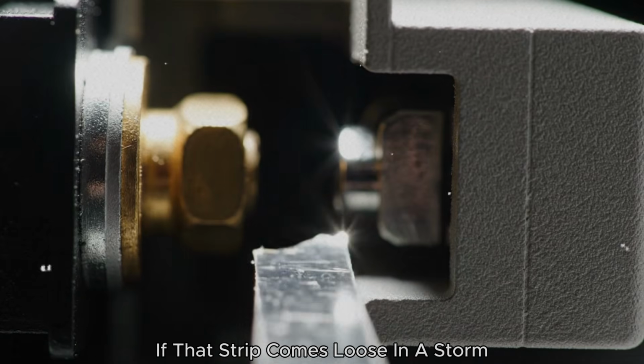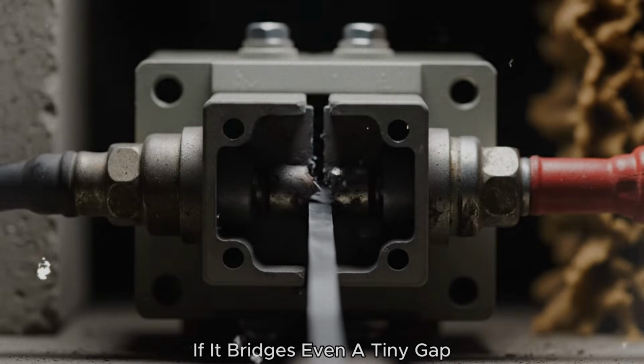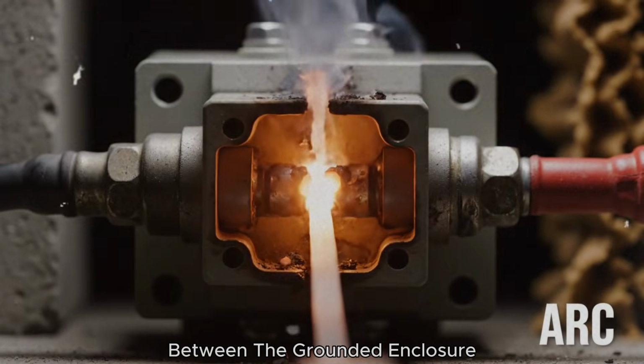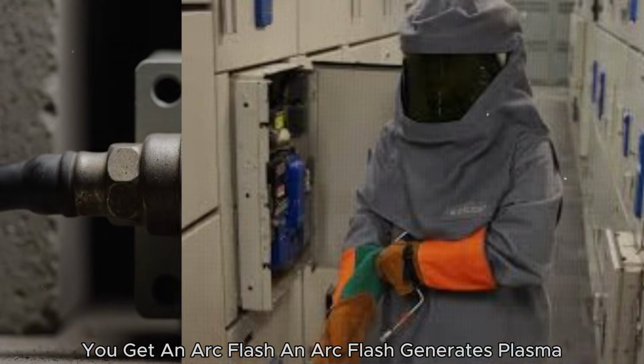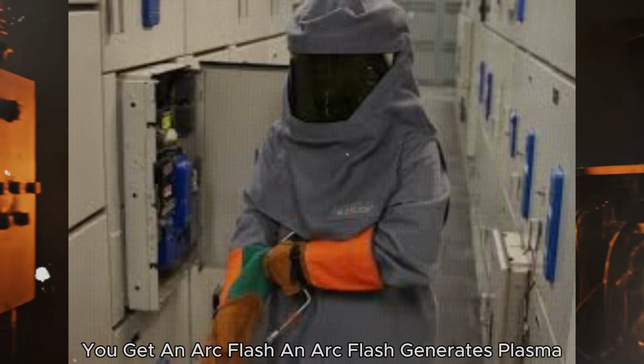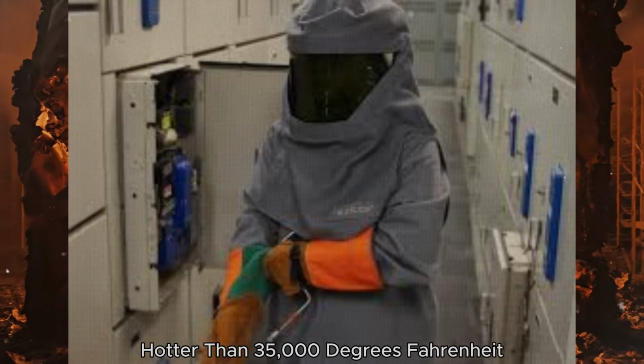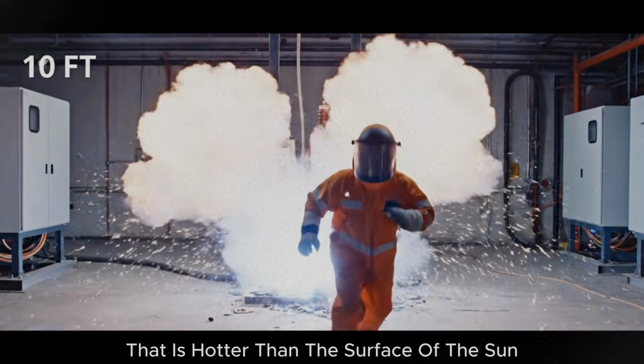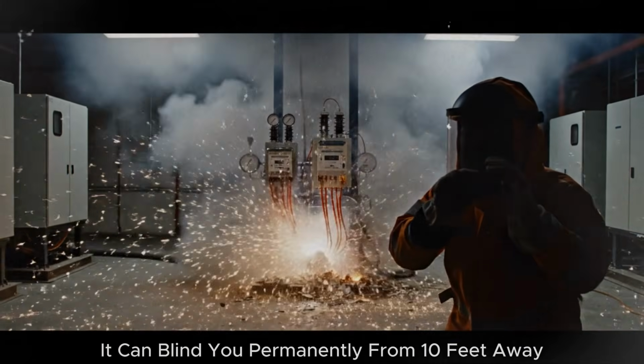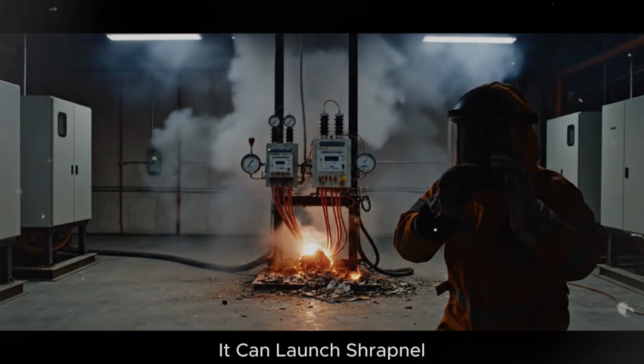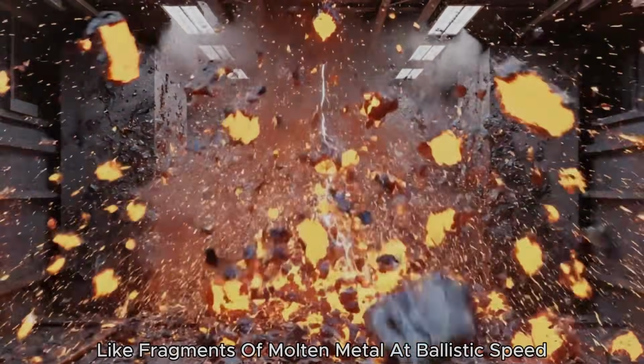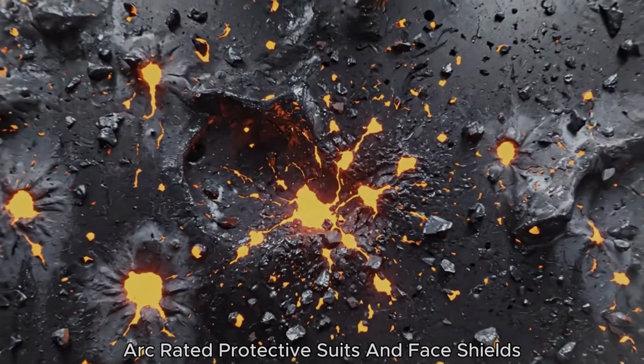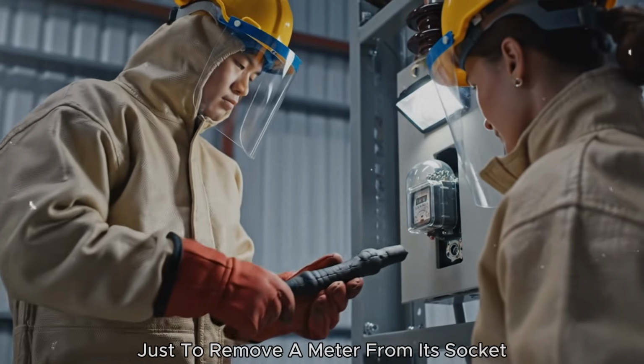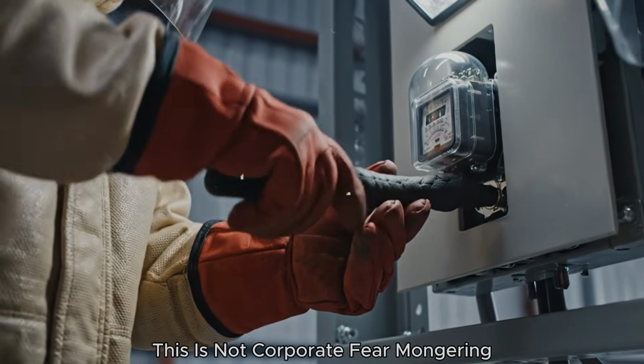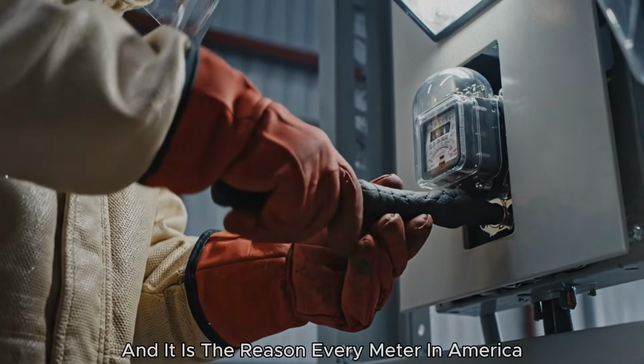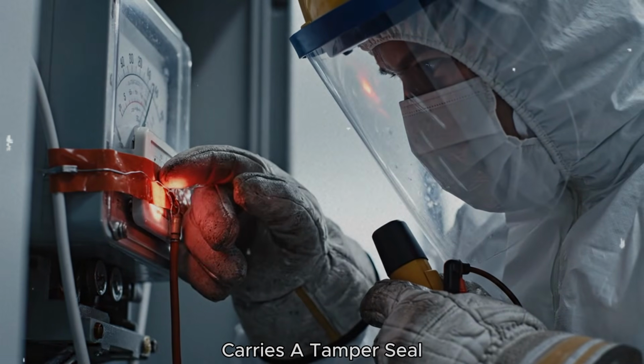If that strip comes loose in a storm, if it slides behind the housing, if it bridges even a tiny gap between the grounded enclosure and a live, uninsulated terminal, you get an arc flash. An arc flash generates plasma hotter than 35,000 degrees Fahrenheit. That is hotter than the surface of the sun. It can blind you permanently from 10 feet away. It can launch shrapnel-like fragments of molten metal at ballistic speed. Trained utility workers wear full arc-rated protective suits and face shields just to remove a meter from its socket. This is not corporate fear-mongering. This is physics, and it is the reason every meter in America carries a tamper seal.